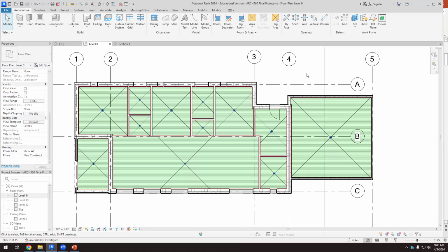There's a boundary, so this is a heated space, and there's this line, this wall is separating it from something that is not outdoor, but it's not heated. Okay, so the temperature in this garage is not a comfort temperature. If we have 70 Fahrenheit here, we won't have 70 Fahrenheit there. So it's an unconditioned space. So depending on the outdoor temperature, if the outdoors is 0 Fahrenheit, maybe the temperature in this garage would be 40, 50 Fahrenheit, depends.